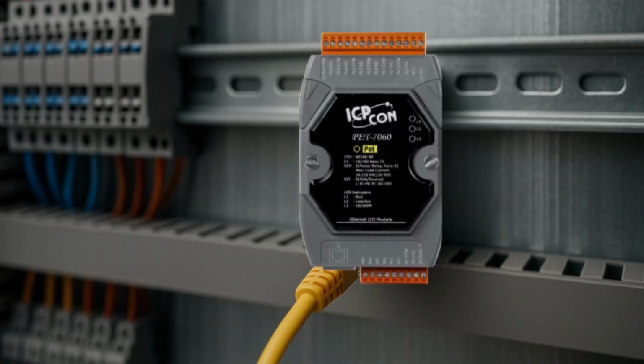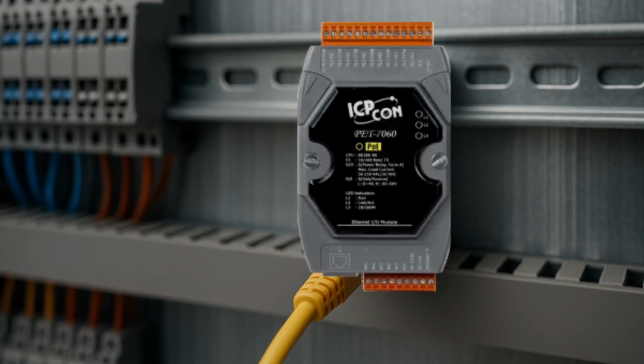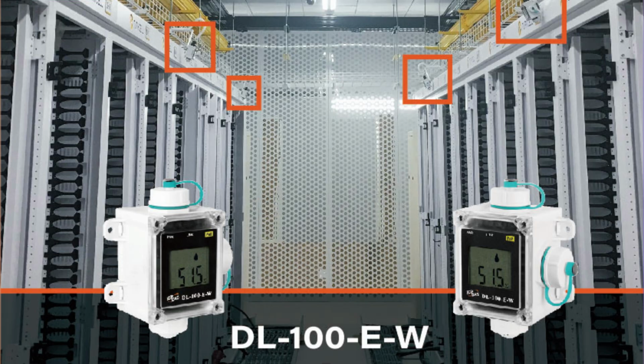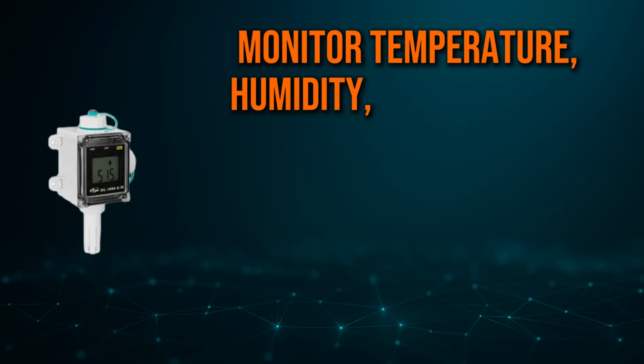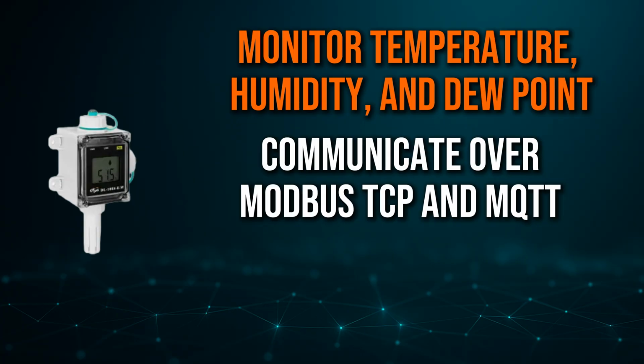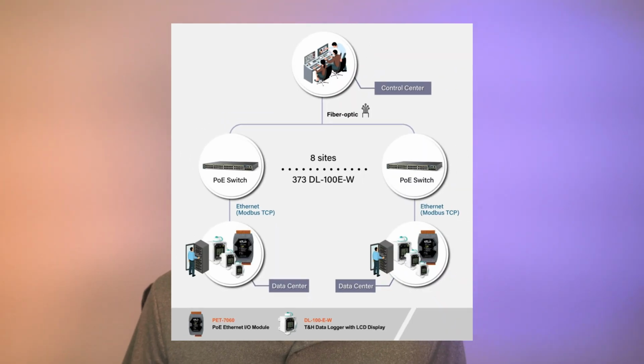Each module is PoE powered, meaning it runs both power and data through a single cable, simplifying installation, reducing wiring, and making the entire system more reliable. Inside each room, we installed DL100 EW remote temperature and humidity data loggers. These devices monitor temperature, humidity, and dew point and communicate through Modbus TCP or MQTT. That means they integrate seamlessly with modern SCADA and building management systems without requiring any additional hardware or coding. All of the field data from every door and every sensor is transmitted over Ethernet back to the control center. From there, the SCADA system aggregates everything in real time: door status, relay commands, temperature and humidity readings, and alarm events. The result is a single unified dashboard that shows every room, every threshold, and every condition at a glance.